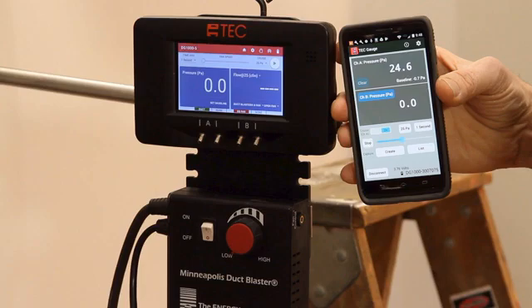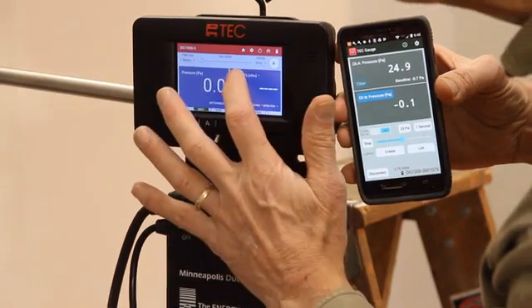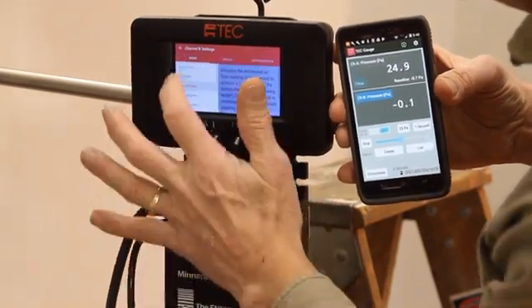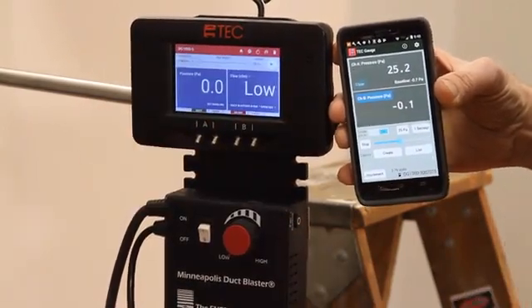On the DG-1000, touch the mode area and change the mode to pressure flow. Confirm that the ring configuration on the gauge matches the ring configuration on the duct blaster fan.